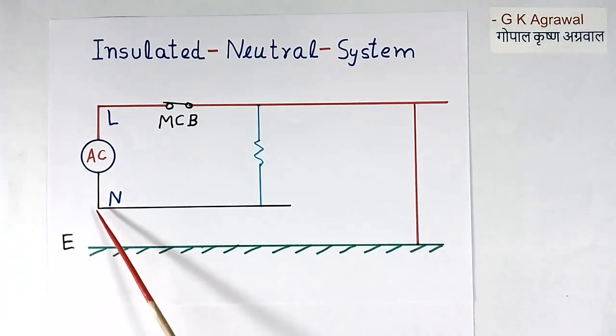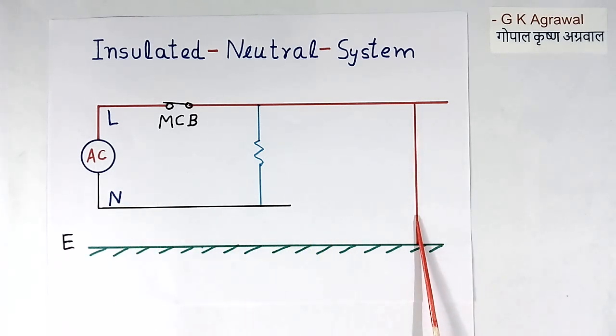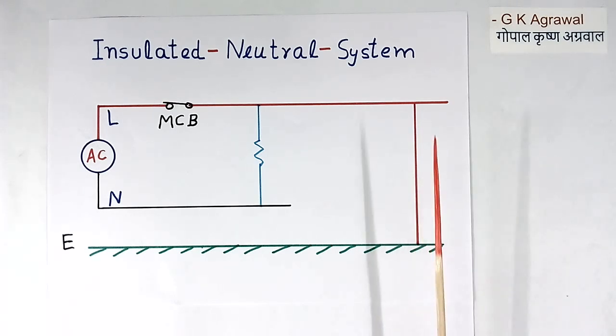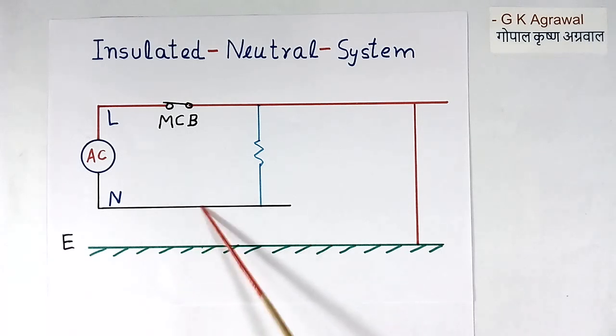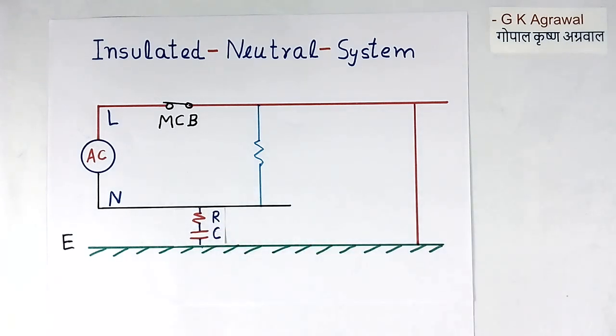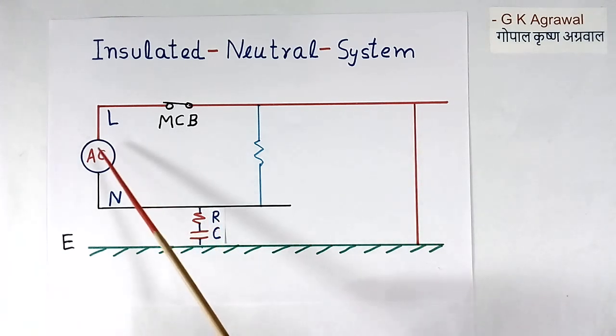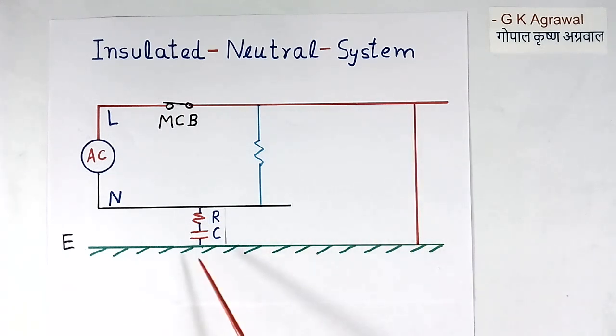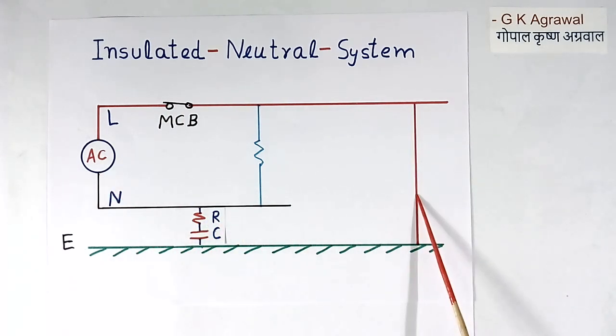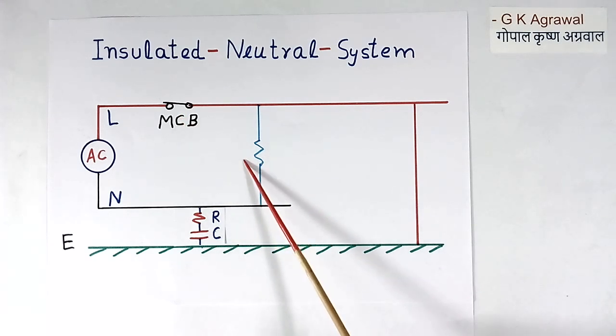In this system, neutral is floating. I have shown a fault here permanently just for explanation — the fault will not be permanent. We connect an RC between neutral and earth. Now neutral is not floating, but the values of R and C are such that the impedance is very high. So in case of a short circuit, current will flow, but very less current will flow because of the high impedance. So the MCB will still not trip, and the load will continue to work.